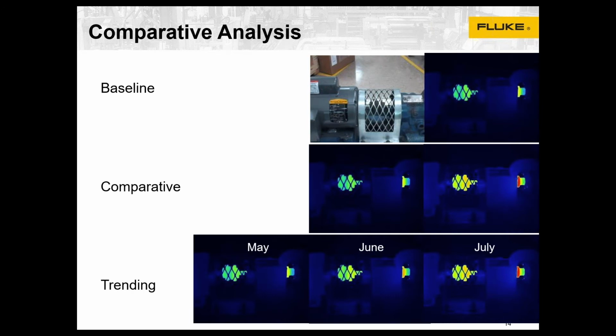Another good approach is comparative. Let's say you have multiple motors or pumps under similar conditions and loads. You can compare between assets to see if anything jumps out, for example between the center, left, and right images. You don't know exactly what the temperatures should be, but you can see the bearings on the right are hotter than the ones on the left, so that asset deserves further attention. You're screening, narrowing down with that comparative approach.